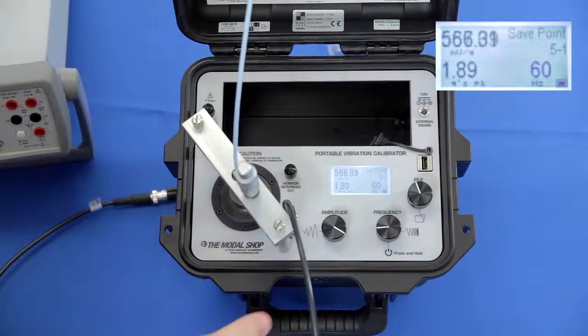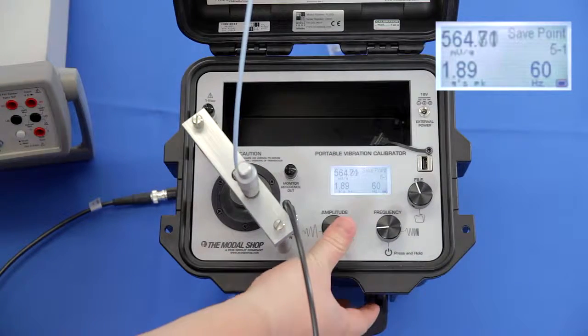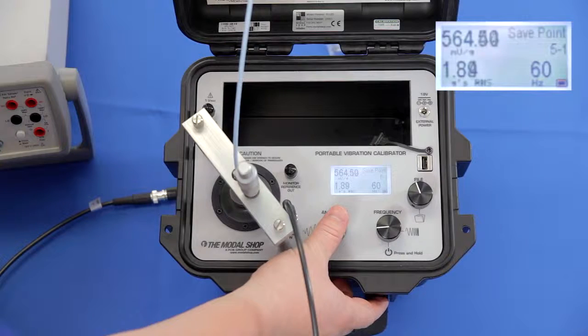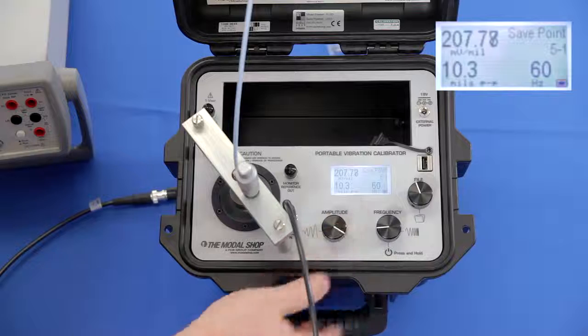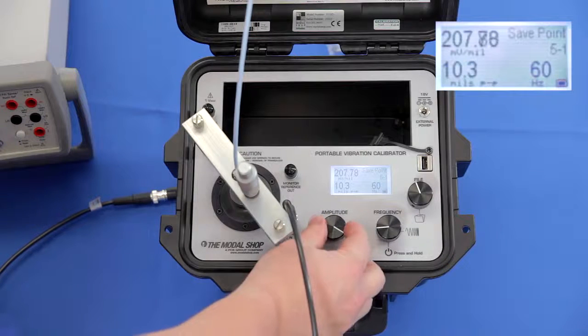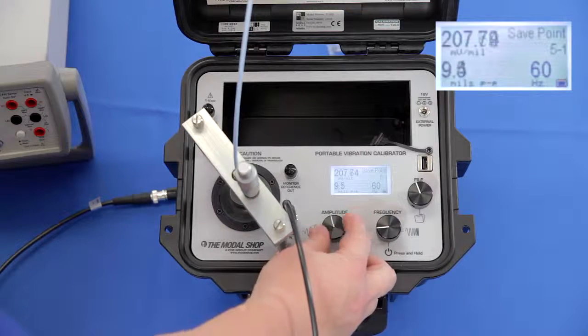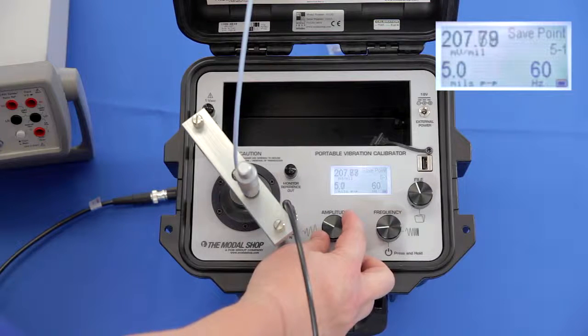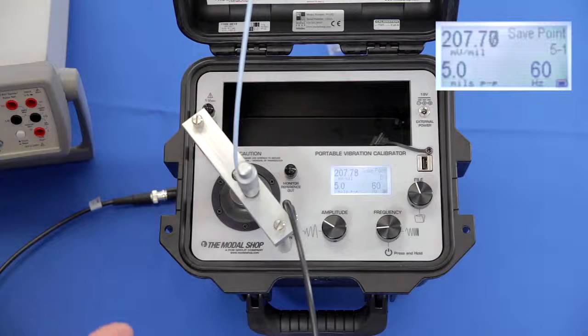Like so. And now I want to change my amplitude scale to mils peak to peak by pressing the amplitude button. You'll see I scroll through G's and inches per second, and now I'm at mils peak to peak. And I'm going to start off at 5 mils peak to peak. The output of my proximity probe should be 200 millivolts per mil. You can see I'm at 208 millivolts per mil, reading slightly high.